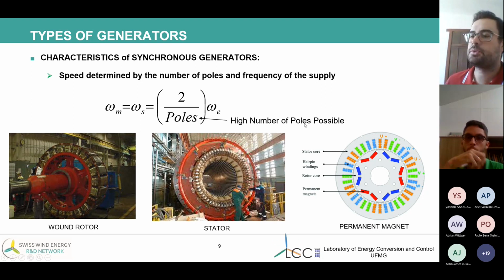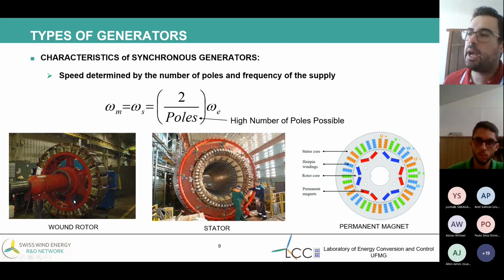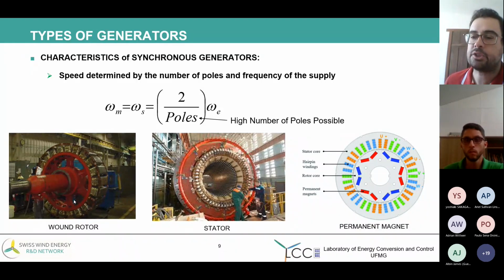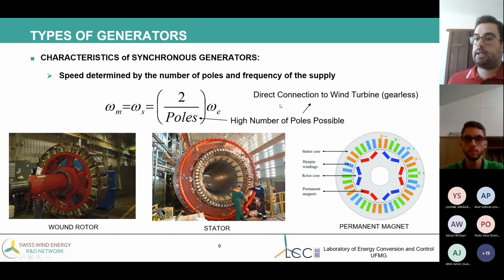A characteristic of synchronous generators is that a high number of poles can be constructed. We see several poles here. For wind applications, we can have 100 poles. It's possible. And what's the advantage of having a high number of poles? The possibility of direct connection to the wind turbine.